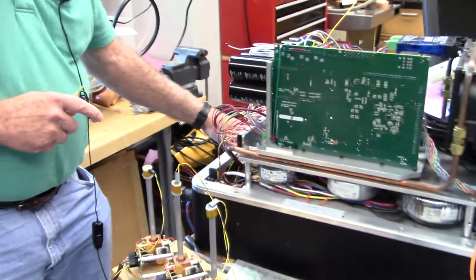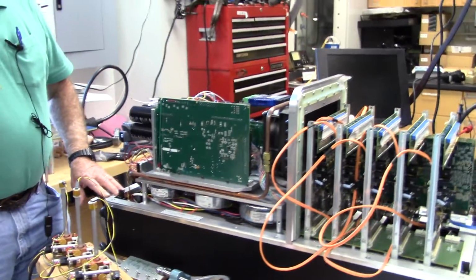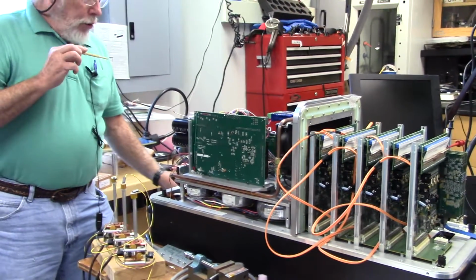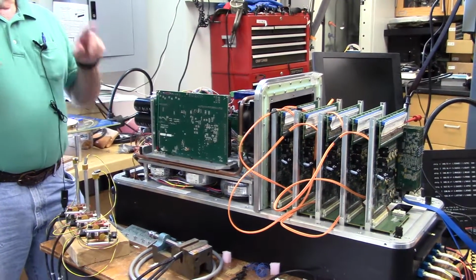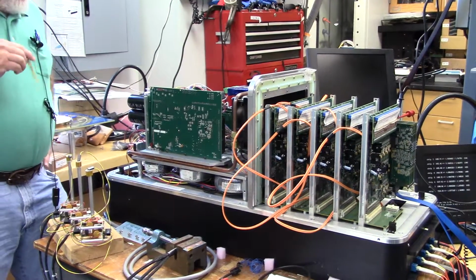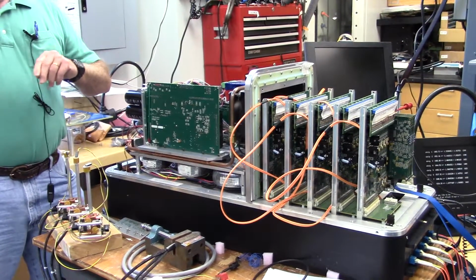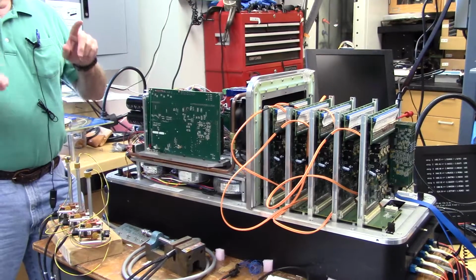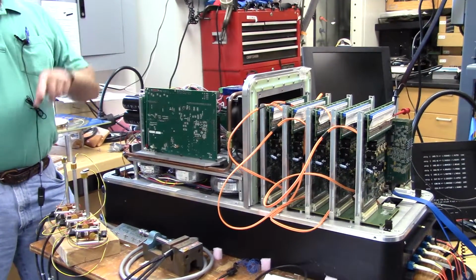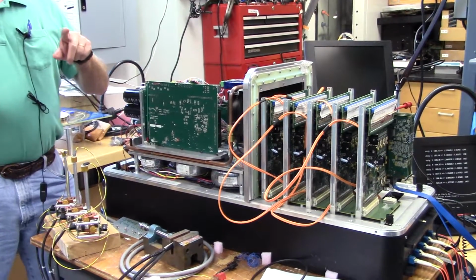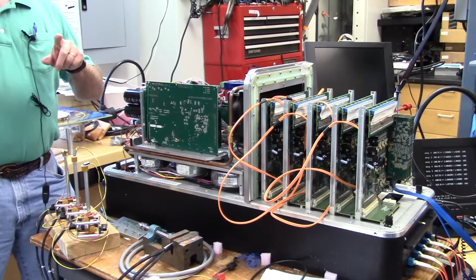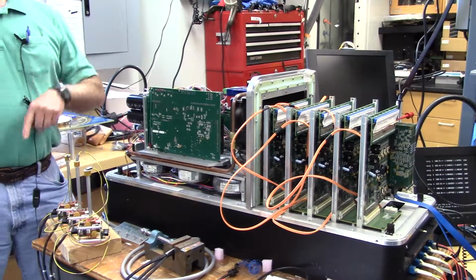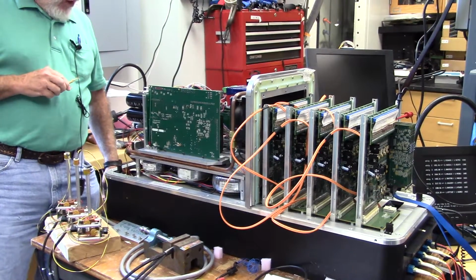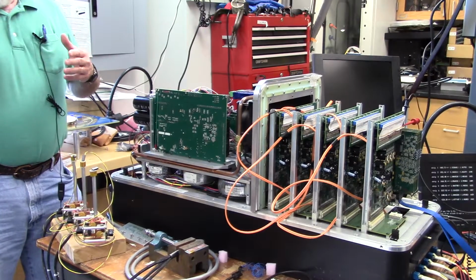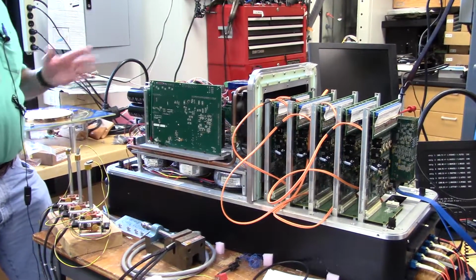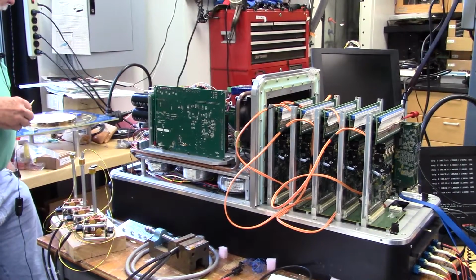It is 220 volt coming in. For many people in the 220 volt world, it'll seem a little strange because if you measure, there are two hots that are 180 degrees out of phase, and it's only the voltage between those two hots that's 220 volts. I did that so that we can use a shielded cable, and the leakage currents through the shield are very low, because you've got one going up and one going down at the same time. The net result is 220 volts top to bottom, but the shield only sees the leakage current from the difference between those two voltages, which is nominally zero, so there's very little leakage current through the shield. Otherwise, with all the capacitance between a single hot conductor and the shield, you'd have quite a bit of leakage current there, and it's just inelegant, to say the least.